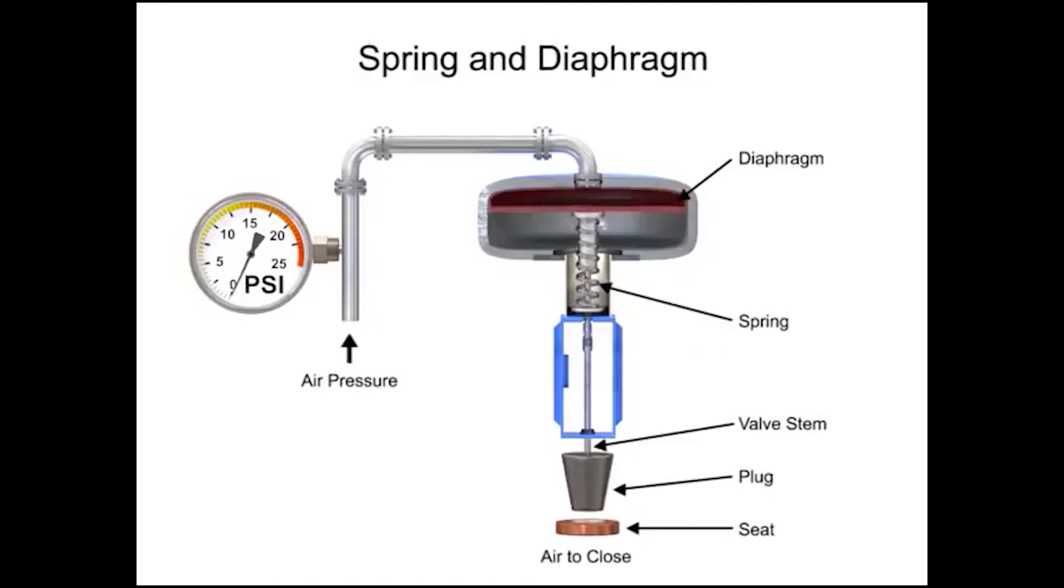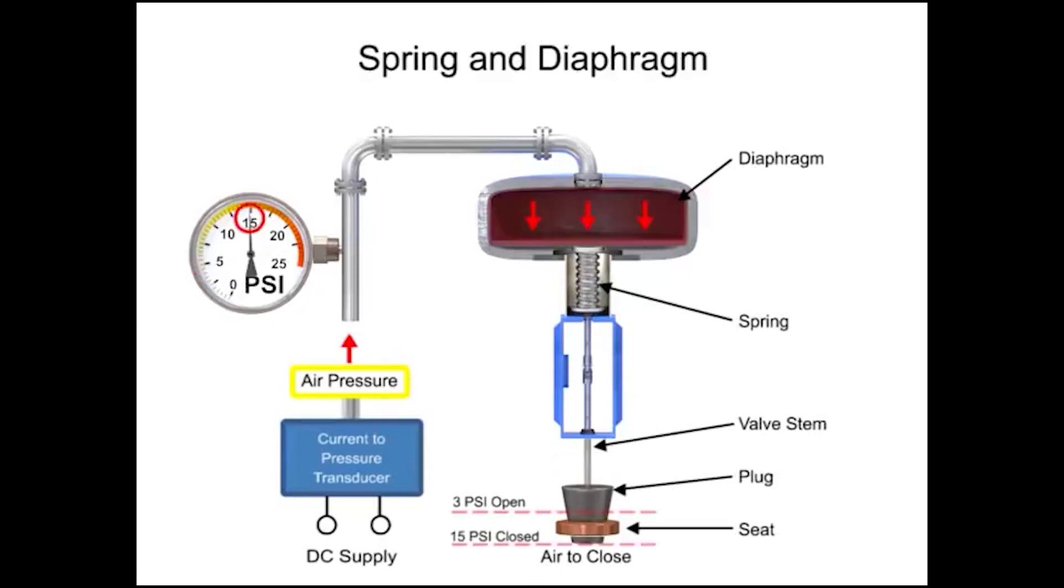To vary the position of the restrictor and flow through the valve, a current to pressure transducer can be used to provide a 3 to 15 PSI signal to the diaphragm. At 3 PSI, the valve is maintained open and at 15 PSI, the valve is maintained closed. Pressures between the 3 to 15 PSI range proportionally change the flow of the valve. For example, a pressure of 9 PSI applied to the diaphragm moves the spring and valve stem to 50% of operating range.